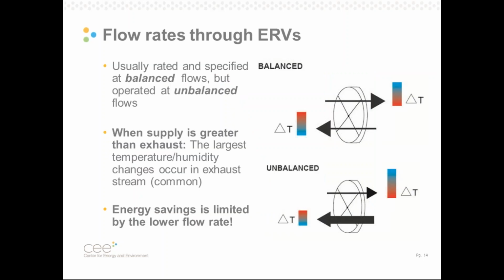There's one other note I want to talk about when we consider the performance of ERVs. The flow rates really matter. In this study, we find that units are usually rated and specified at balanced flows, but in actual operation they're operated at unbalanced flows. What does that mean? Well, balanced flows means that the exhaust and supply flow rates are about the same. Say they're each 1,000 CFM.